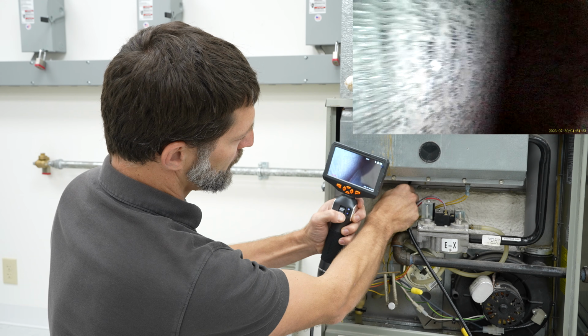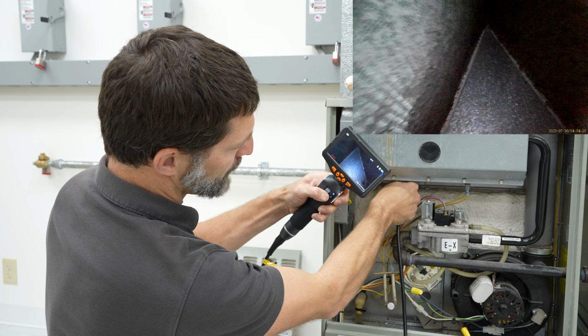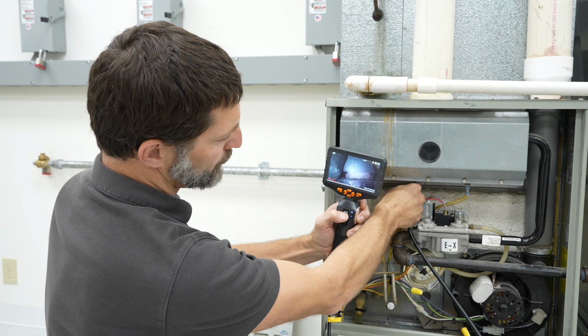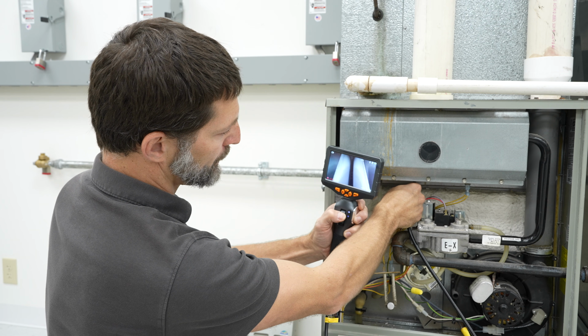So we can see the coil right there, and we can pan down, and we can see that especially the back of it is clogged with dust. So we know that we're going to have to take this out and clean it. So you can see that this is really fully clogged up right there. You can see a lot with this video scope, and you could even look down at the furnace heat exchangers. And of course you could also use this as a double verification after you measure static pressure as well.